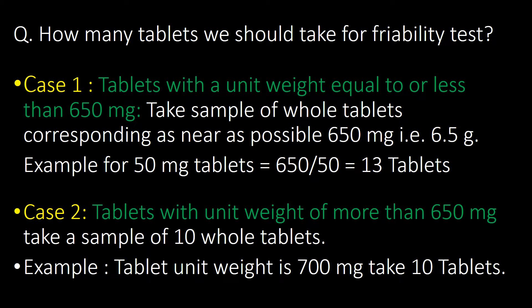Now consider case two: if tablets have a unit weight of more than 650 mg, take a sample of 10 whole tablets. For example, if a tablet has a unit weight of 700 mg, we should take 10 tablets for the friability test.